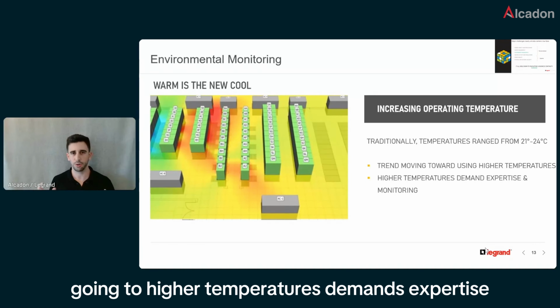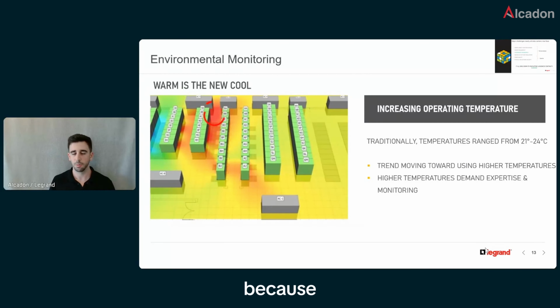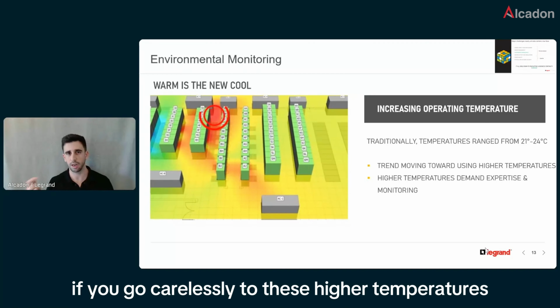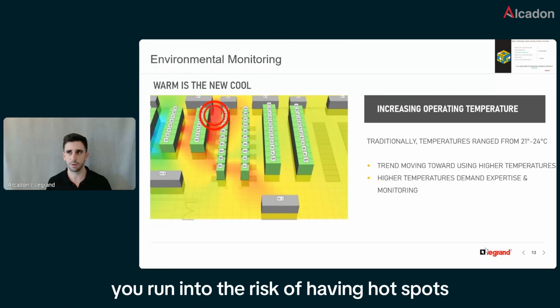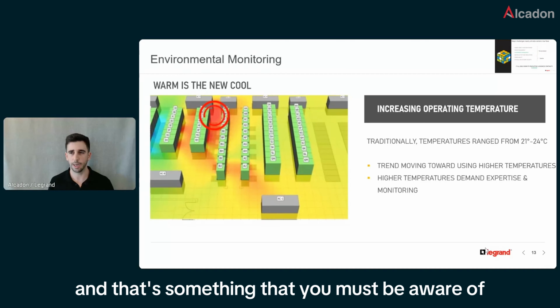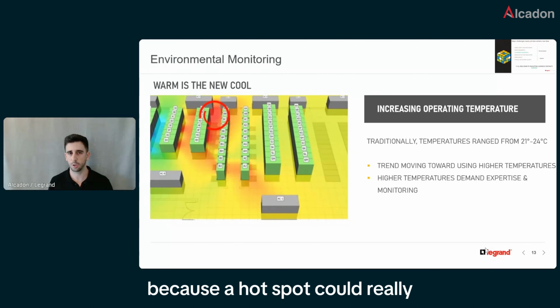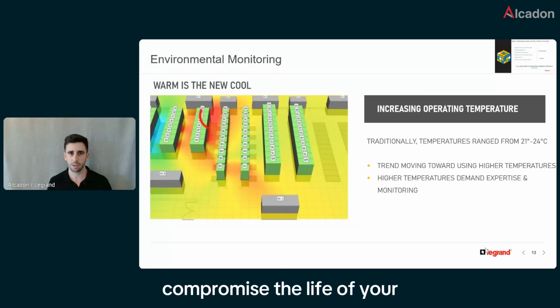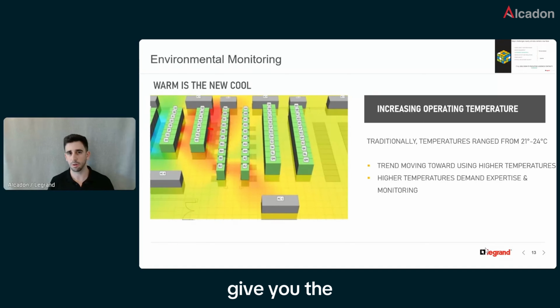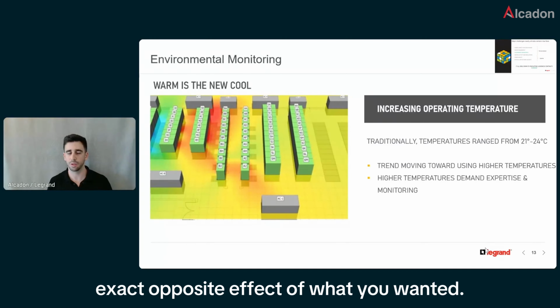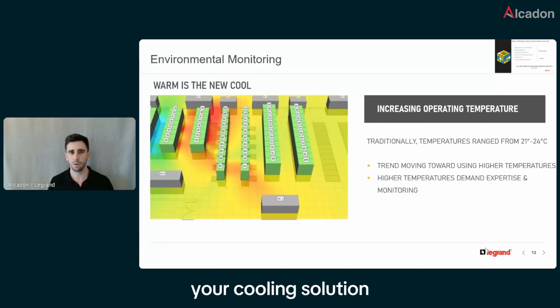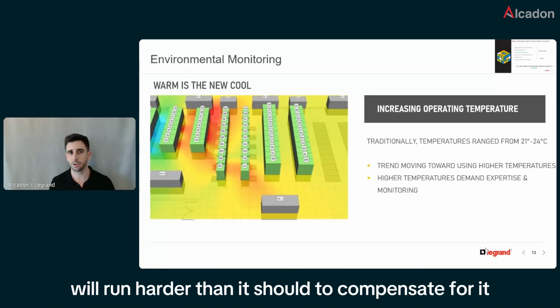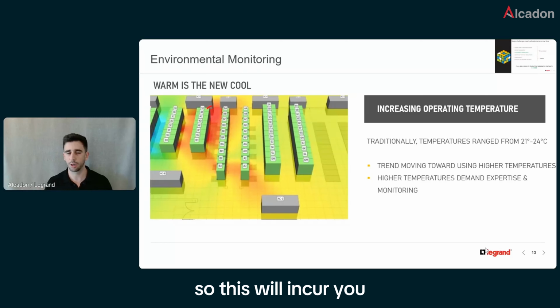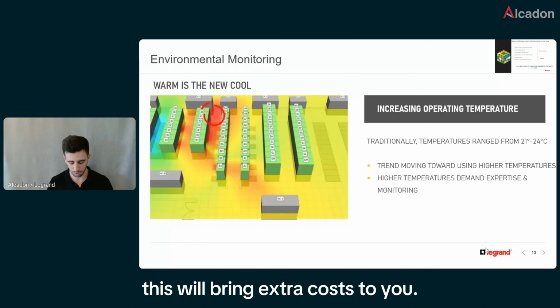Of course, going to higher temperatures demands expertise, knowledge, and monitoring, because if you go carelessly to these higher temperatures, you run the risk of hotspots. A hotspot could really compromise the life of your IT equipment, and could give you the exact opposite effect of what you wanted. If you have a hotspot, your cooling solution will run harder than it should to compensate, which brings extra costs.